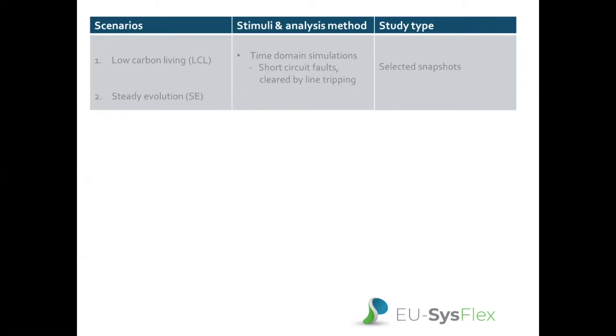So first things first, we have two scenarios, low carbon living and steady evolution, where low carbon living is the more ambitious scenario with high renewable penetrations. We assessed 800 short circuit fault contingencies. We're using time domain studies, and because each scenario had 8,760 hours of operation, because they reflect the full year, to keep things a bit more manageable, we decided to select snapshots for each scenario and just study those snapshots for all of the contingencies. So we had about 40 snapshots for each scenario, and then studied every contingency for every snapshot.